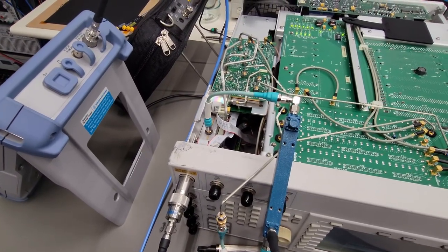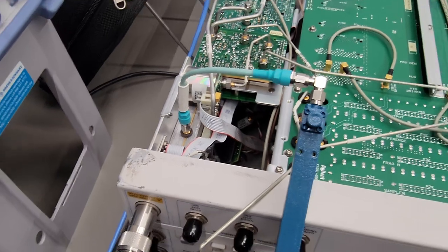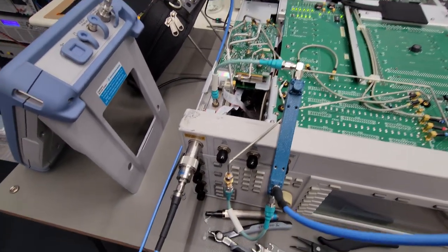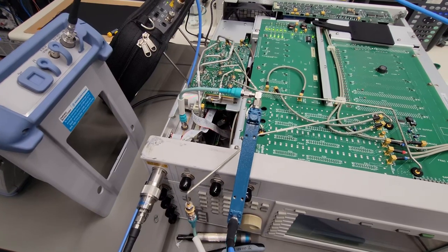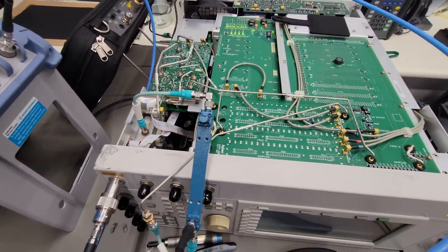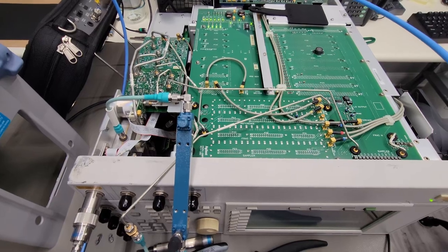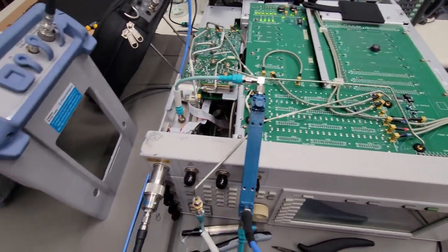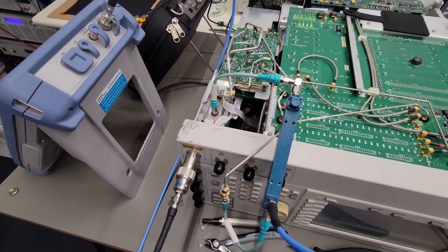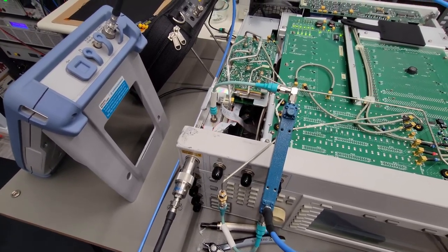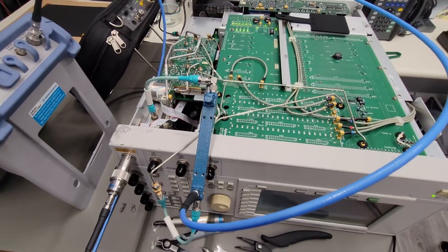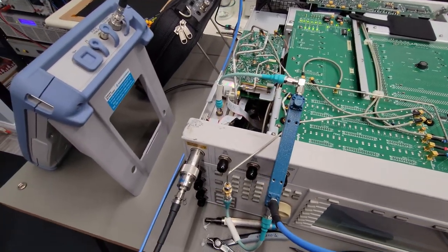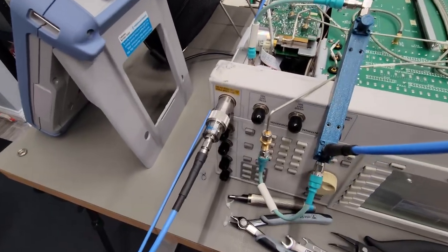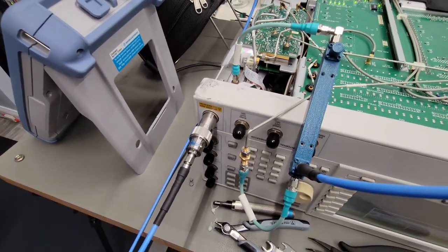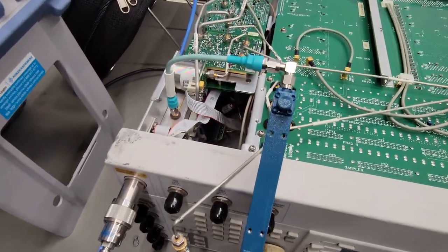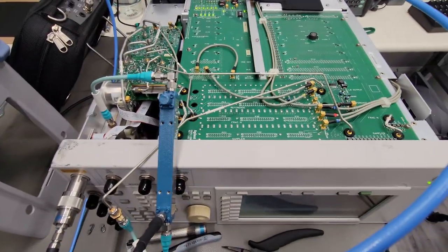The detectors in the low band and high band both take the AC signal, rectify it to DC, and then that DC is compared to an internal DC signal level that's created by a DAC inside the instrument. And based on that comparison, the instrument then knows what the relative power level is. And of course, when it's calibrated and characterized at the factory, those DACs are trimmed so that when you set 0 dBm at the output connector, you really are getting 0 dBm, and the instrument knows what those offsets are to compensate for all the paths internally.